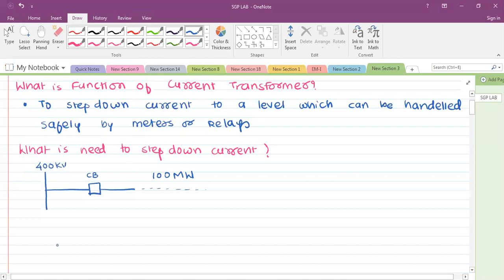It is 100 megawatt divided by root 3 upon 400 kV. So it will come around 144 ampere. Root 3 - have you considered it? We are talking about a three-phase system, so don't directly divide power by voltage. Make sure you use the equation P equals root 3 VI. Cos phi we are not considering right now, just for simplicity - let us consider power factor as 1.